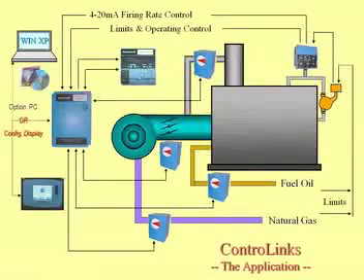So whether this is a FireEye system or Pyronics or Honeywell, whatever it happens to be, as long as it's a full function programmer, it will work and handshake properly with the Honeywell ControLinks. On the right-hand side, of course, you see your traditional level controls. There could be any number of different safeties and limits in here. In this picture, we're showing Honeywell's integrated pressure control. It does your modulation, your high limit, and it does your operating control functions all in one piece.